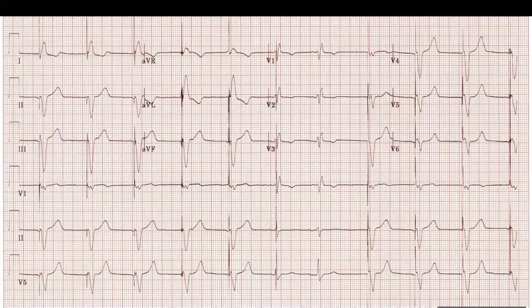So what could cause that? Either the QRS happens at almost the same time as the pacing spike, so the pacing doesn't have time to transmit and the intrinsic QRS takes over. Or sometimes we call this safety pacing. So for example, the device is not sure if this is an intrinsic QRS or not, so it would deliver a pacing spike just to avoid a dropped QRS.